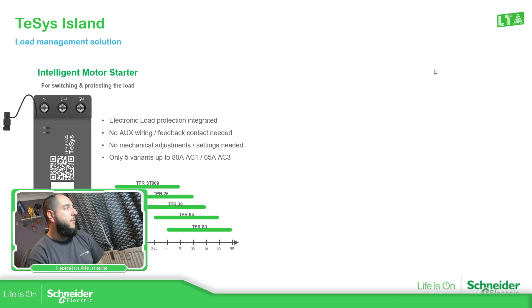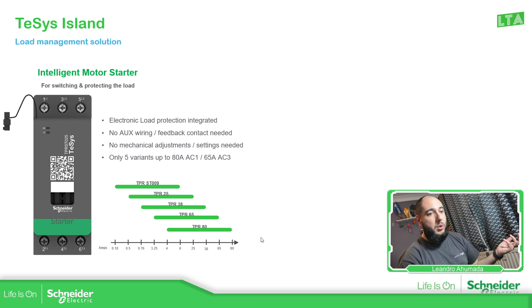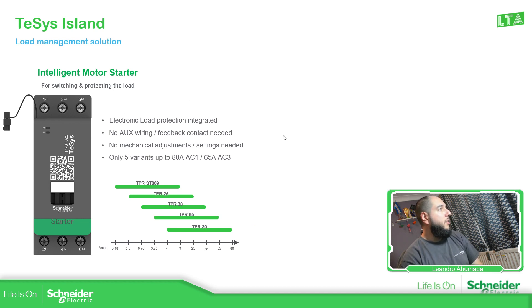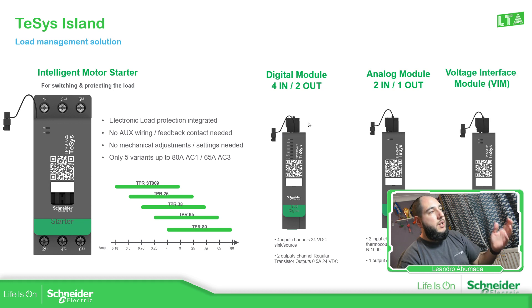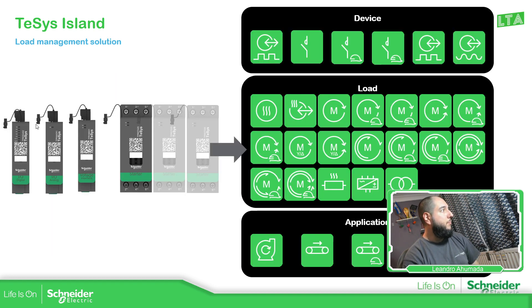The starter module is one of the main components for controlling the motor. We have different sizes depending on the motor power needed, going up to 80 amps. If you need more than that, you'd need to go with the traditional way. We also have digital IOs, analog IOs, and the voltage interface. The combination of these elements gives us different avatars — for application, for load, and for device.